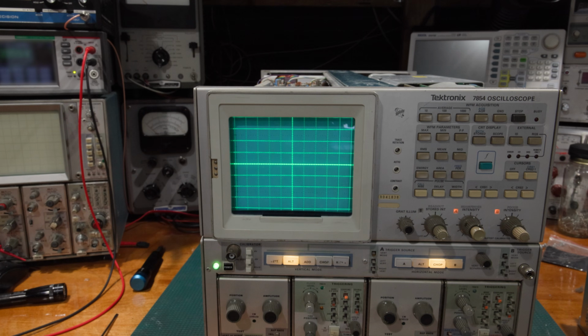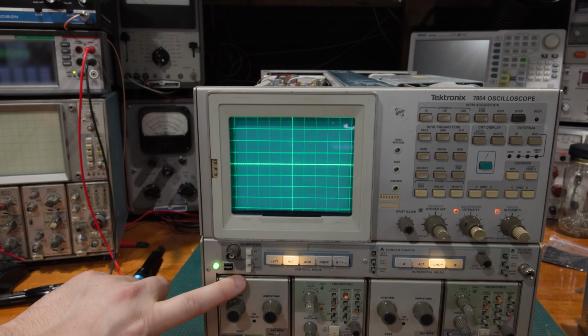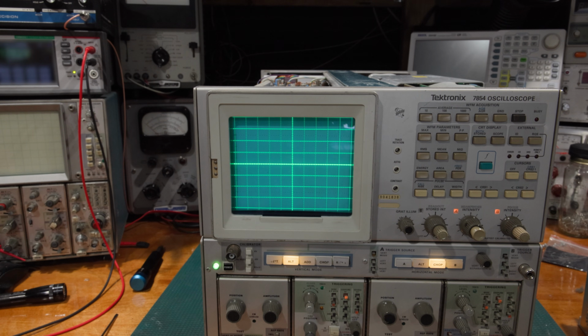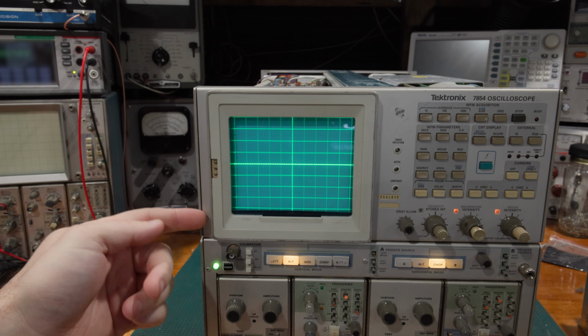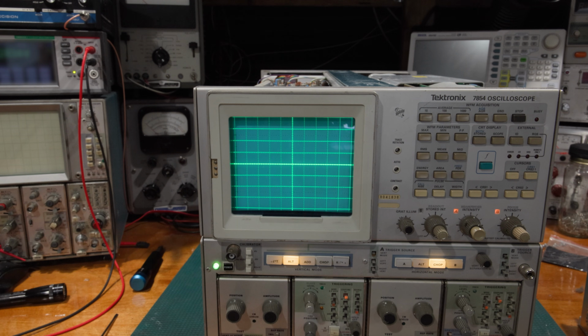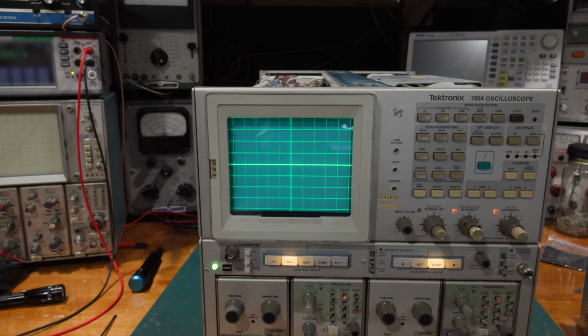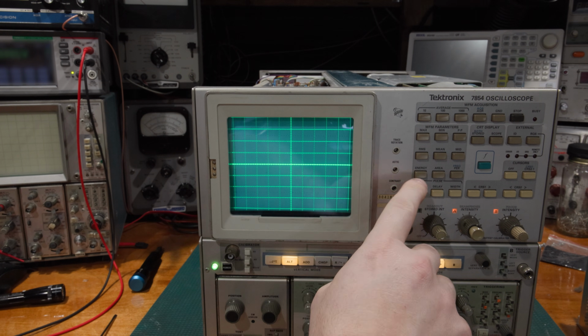That's where these signal standardizers come in. When you do the horizontal vertical gain and you set up this grid pattern, these are truth. So everything ties back to a plug-in. You do the frame, then you do the horizontals, then you do the verticals. Everything ties back into the step gain of one of these signal calibrators, or both in this case. This isn't looking too bad, and we will be able to address the display issues with this scope. But for right now, this is the best we can get because I still have to do vertical and horizontal amplifiers and a couple of other things. So what we're looking for in this one is X and Y alignment. So X will be trace rotation.